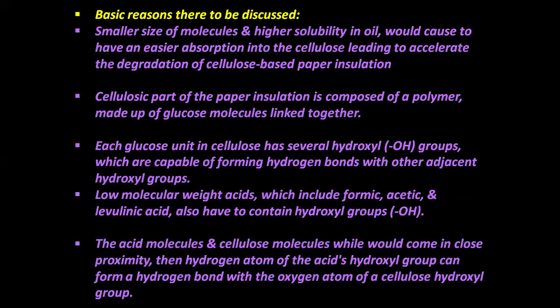Basic reasons to be discussed. Smaller size of molecules and higher solubility in oil would cause easier absorption into the cellulose, leading to accelerated degradation of cellulose based paper insulation.